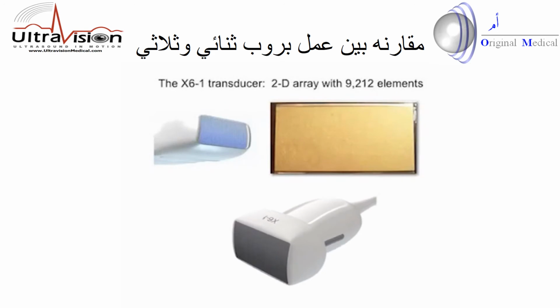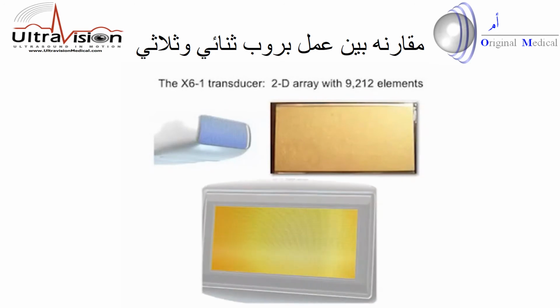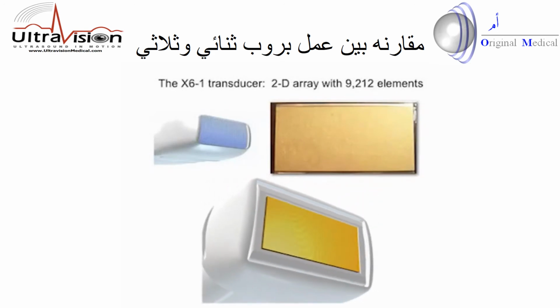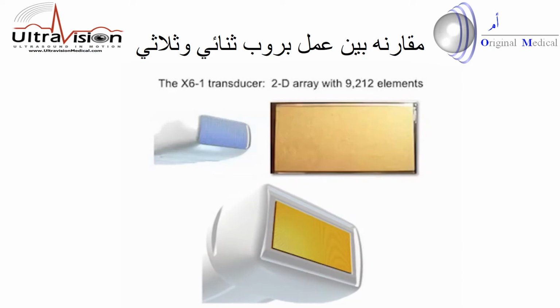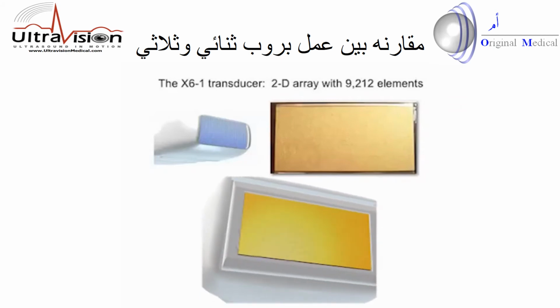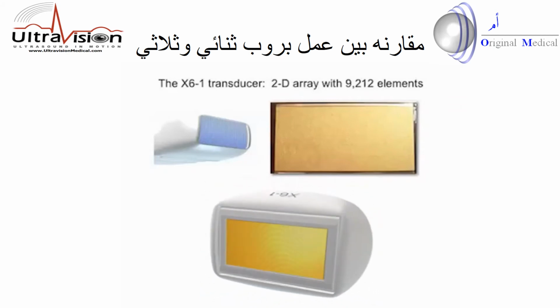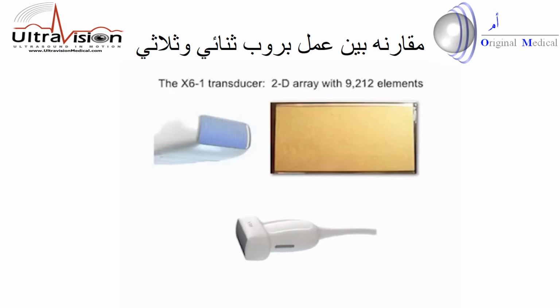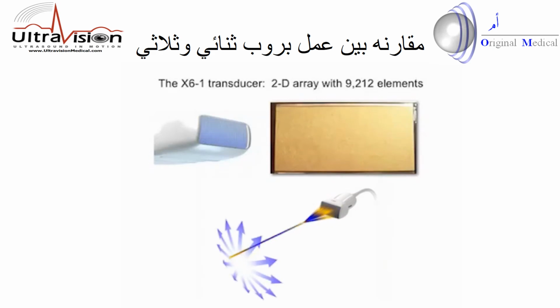It doesn't have a line of elements, it has a two-dimensional array of elements. And although the area of the footprint of the transducer is comparable to that of a conventional abdominal transducer, there are a great deal more elements there, not 100 or 200, but 9,000 elements in the case of the X6-1. And I think you can see immediately that such a transducer, if one had control of all of those elements, could be used in many different modes.